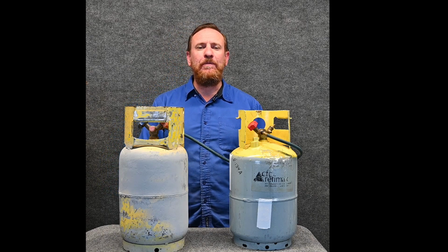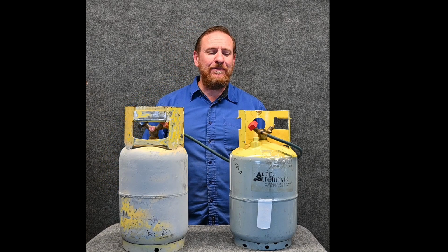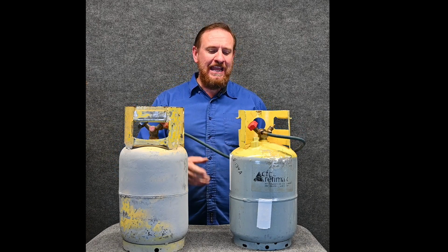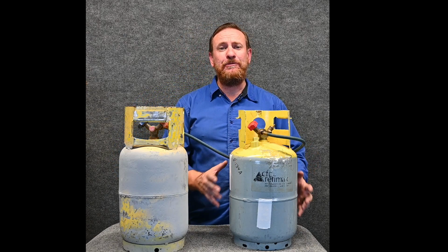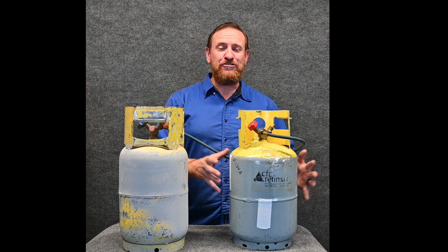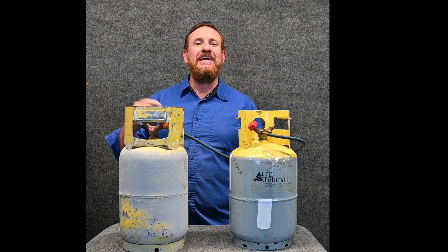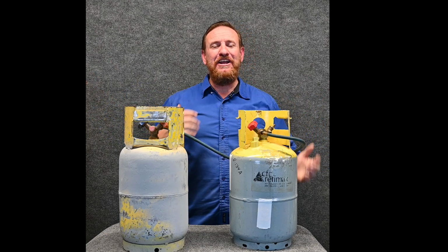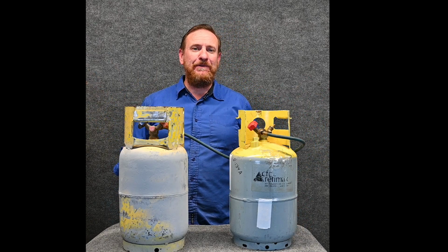I actually talked to one person that worked for a laboratory, and they were able to do refrigerant recovery just simply by hooking a hose up to the unit and putting the tank in liquid nitrogen, or putting liquid nitrogen on the tank, and it dropped the temperature of the tank so dramatically, all the refrigerant would migrate out of the equipment and go to the tank. It's another way of doing recovery. No pump at all needed.